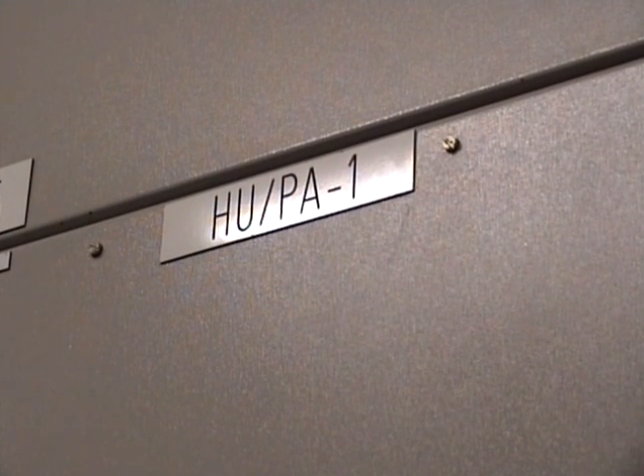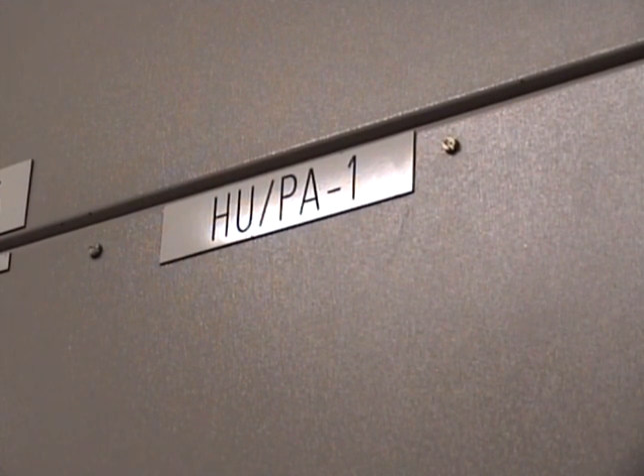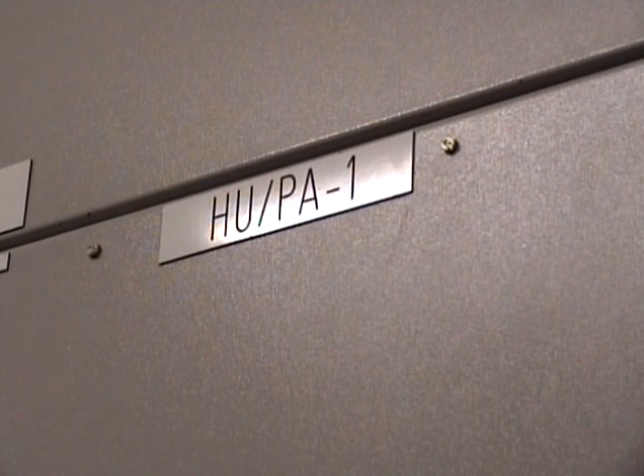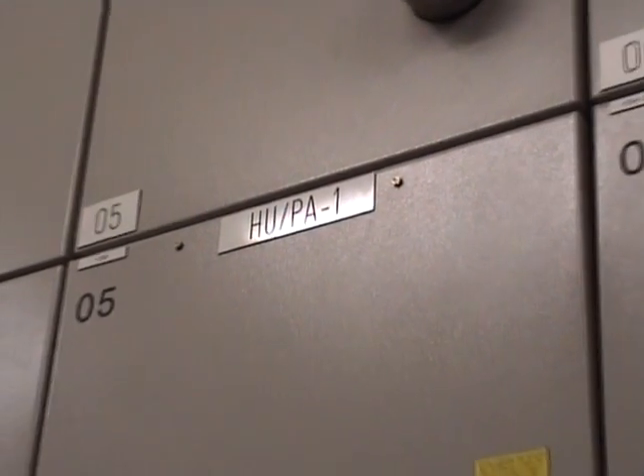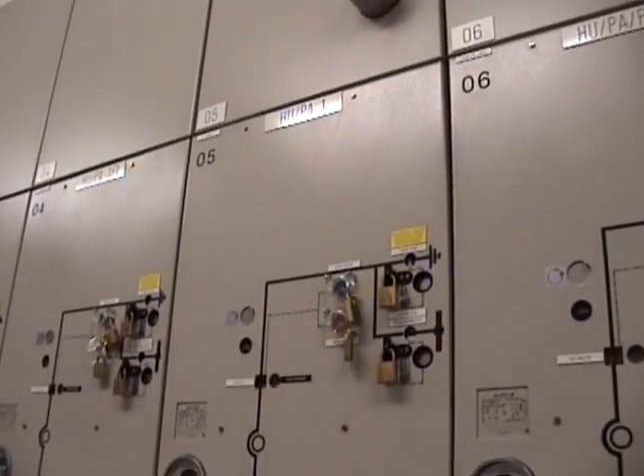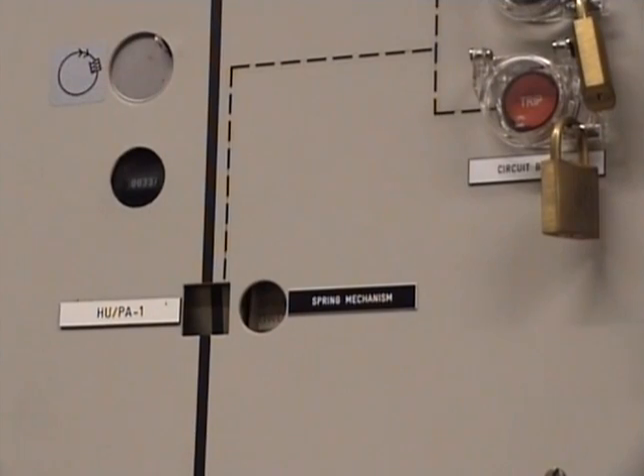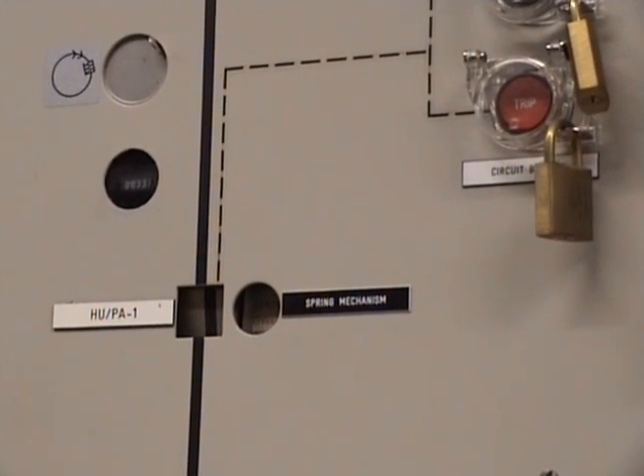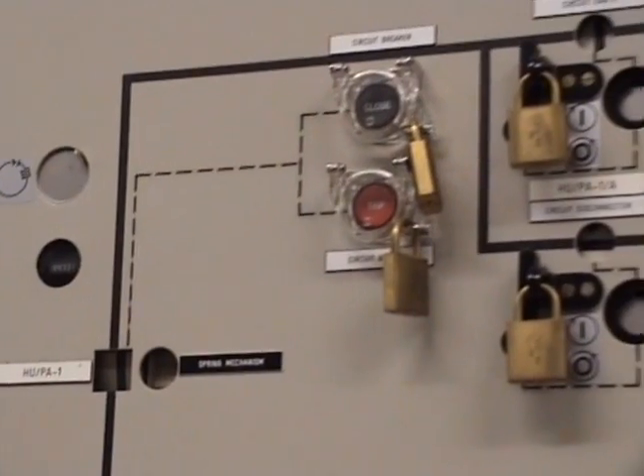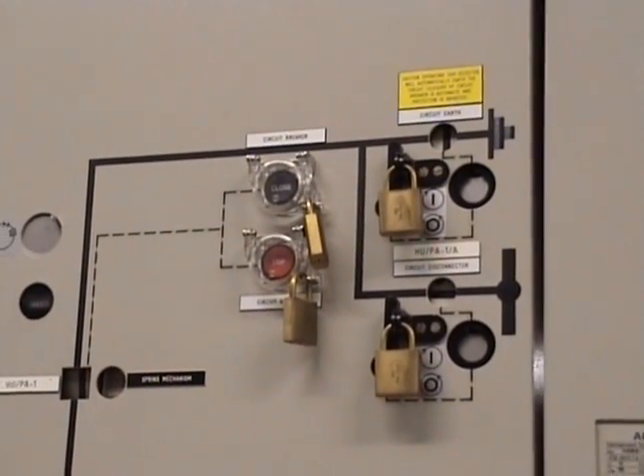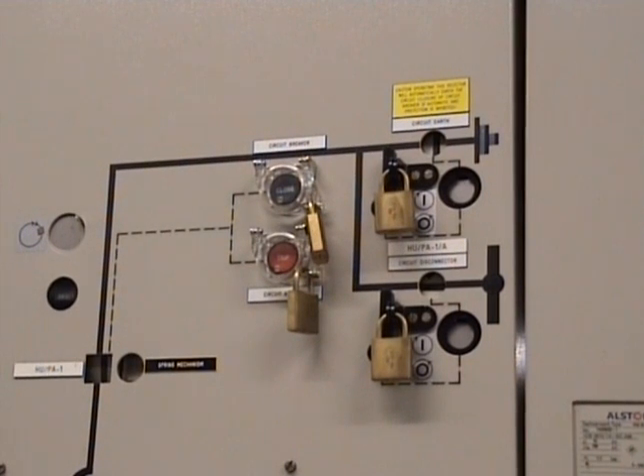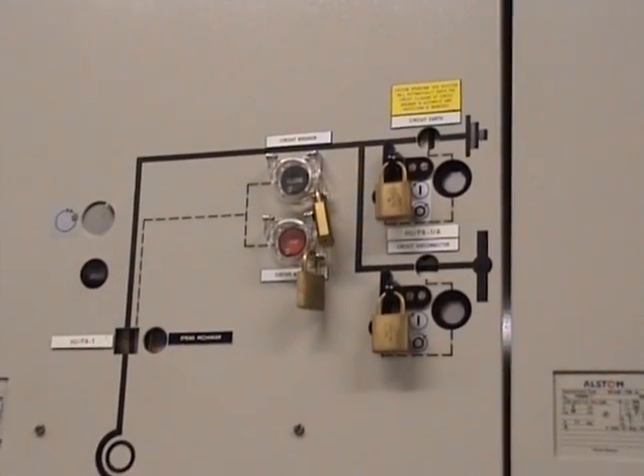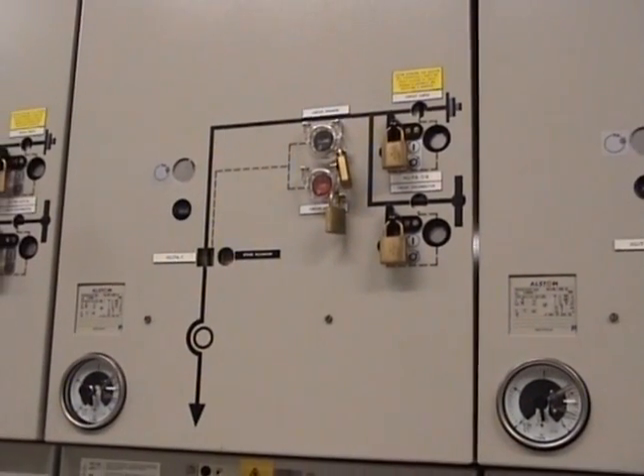We are now going to carry out isolation and earthing of track feeder at Hunsbury Hill, Hotel Uniform Papa Alpha 1. Initially, we see the arrangement in normal feed position. The circuit breaker is closed and the disconnector is closed. Thereby the circuit is from and to bus bar, out through the circuit breaker to the sealing end and onto the overhead.